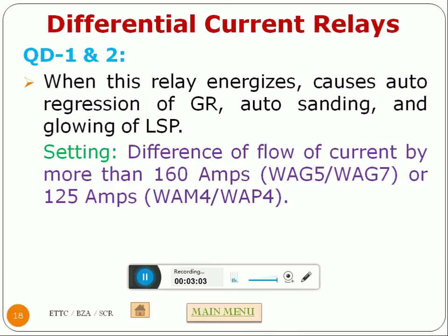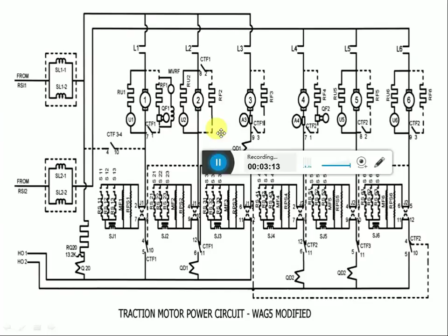QD will de-energize when the difference of current falls to 130 amps in goods locos and 80 amps in coaching locos. These QD actions will then be nullified. You can see QD1 connected between traction motors 2 and 3. It will measure the difference of currents in TM2 and TM3. Similarly, QD2 is connected between traction motors 4 and 5.